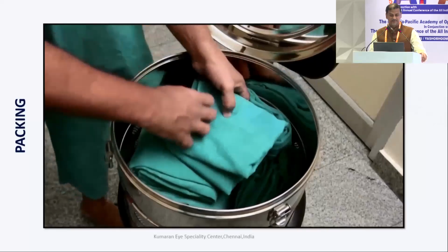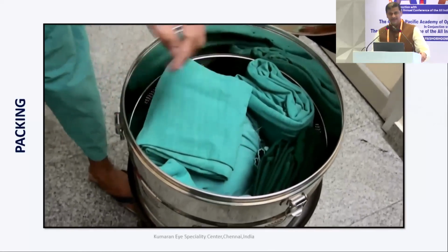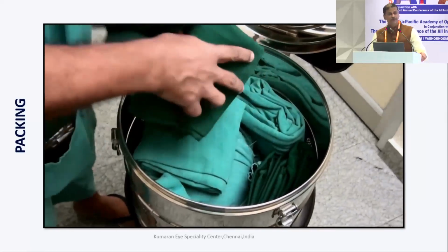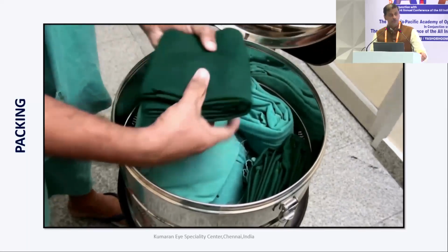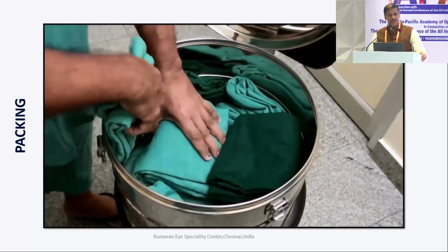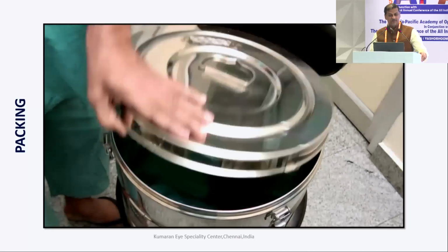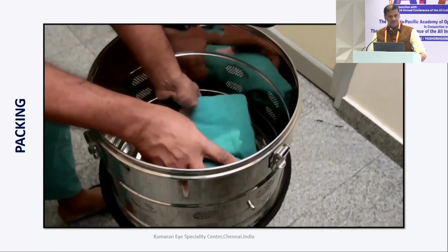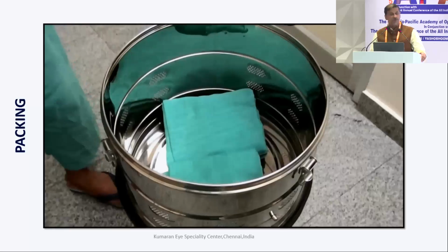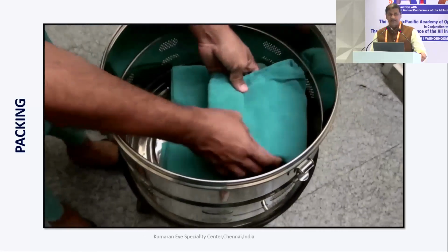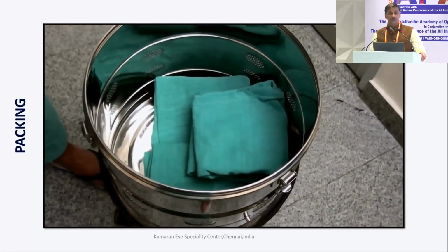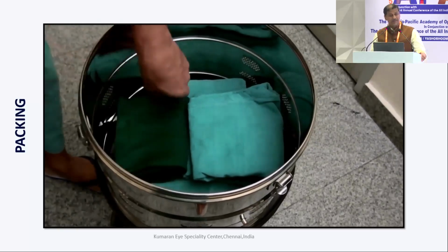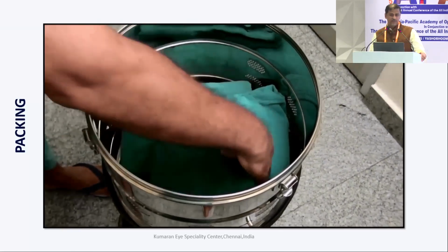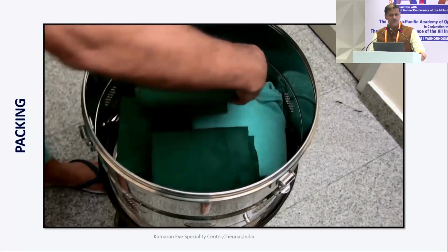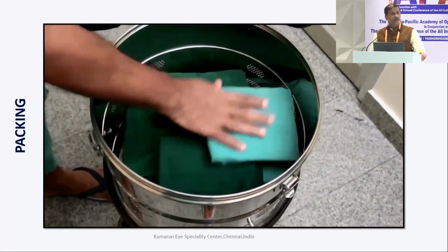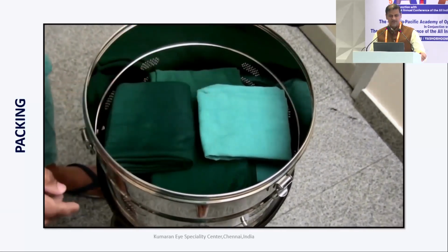Normally, with the latest techniques, a bin should never be used to autoclave instruments, but it can be used to autoclave linen. Here you could see the paramedical staff putting a lot of linen into the sterilizer. This should not be done. You should allow adequate space for the steam to penetrate all throughout. In case you're using your bin to sterilize your instruments, make sure they are kept inside the bin unpacked. This is a very important point which you should keep in mind. Otherwise, just use your bin to sterilize your linen load if you're still using linen for your surgeries.